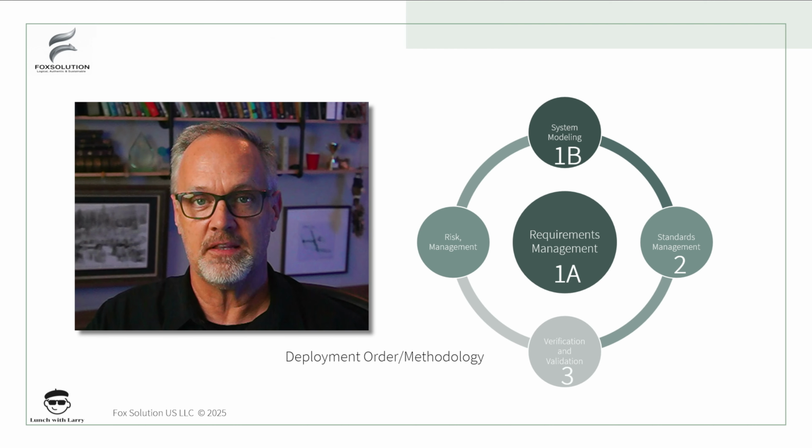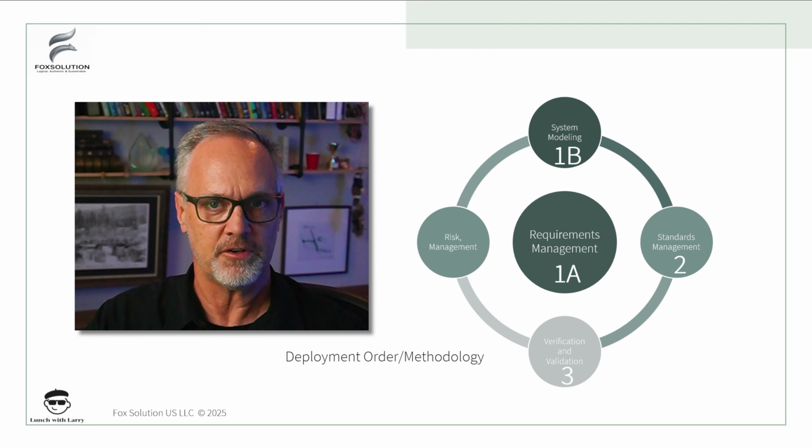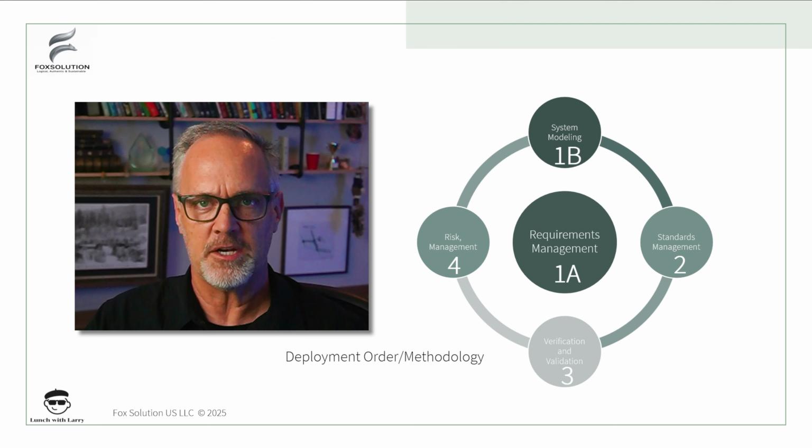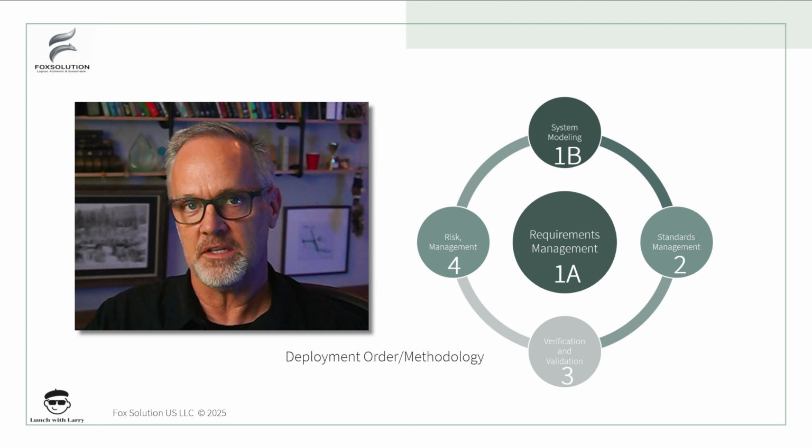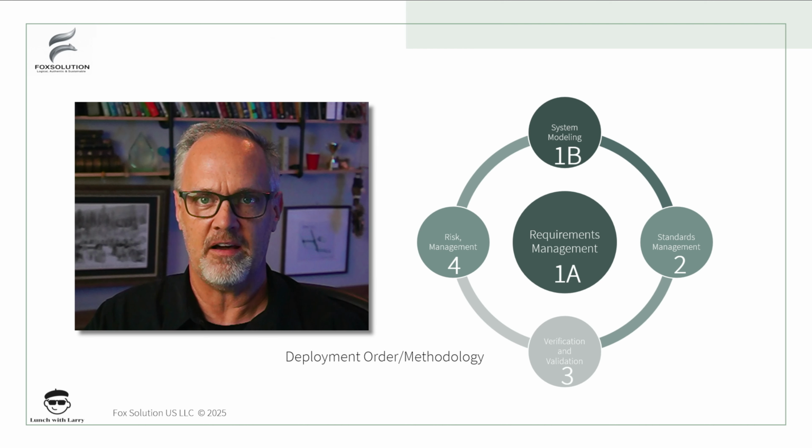Verification and validation, that's really our evidence that the device complies with our definition of good as defined by the requirements. So we want to have that traceability built into the system. And finally, risk management. What is the negative view of the design? What are the things that we don't want the design to do, and what are the mitigations we have and need to have in place to assure that those bad things don't happen?